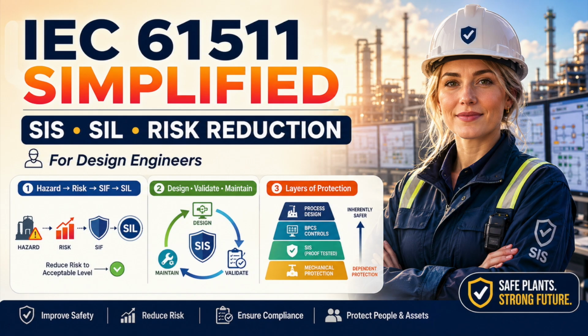That is the raw truth behind functional safety. The safety instrumented system is not the safety PLC. It is not the transmitter. It is not the shutdown valve. It is not the SIL certificate. It is the complete chain of justified decisions connecting the hazard to the safe state. Hazard understood, risk evaluated, BPCS credit challenged, protection layers challenged, required risk reduction allocated, safety function precisely specified, architecture engineered, integrity demonstrated, system validated, performance maintained, changes controlled. Break any one of those links and the SIL number may become decoration.